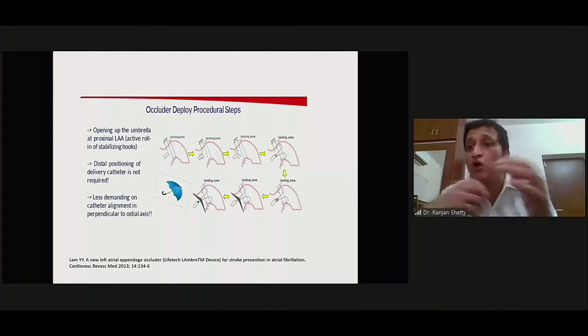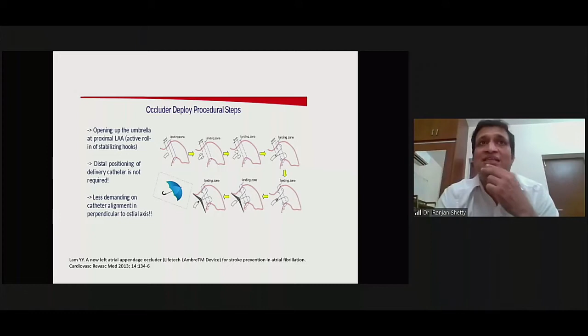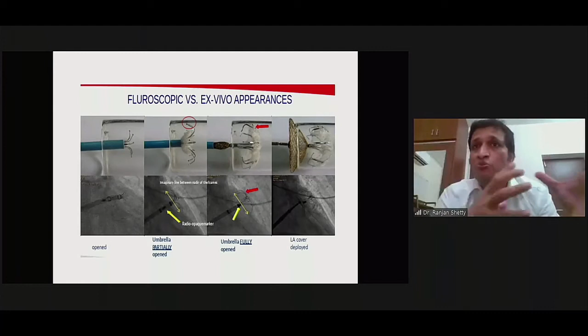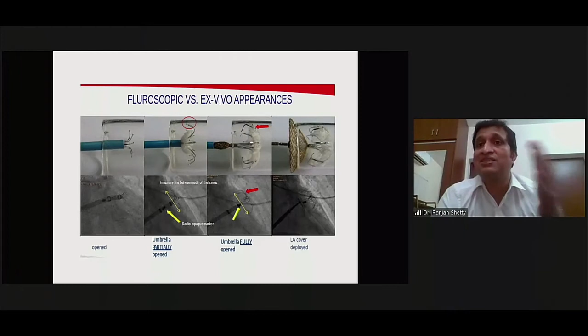Among the devices, this is easy to deploy and it is safer because you're not going too deep, and it's more forgiving. The size variation is allowed, it's a little more forgiving. So just to demonstrate the same thing, you're bringing the hooks out of the sheath here, you're slightly pushing it in, you're reaching the landing zone. As you reach the landing zone, you're unsheathing it further, and more unsheathing will actually lead to opening of the disc. At this point, you find that it's stuck, it's in position, the movement is only in this. So slightly open, partially open, take it to position, keep the anti-clockwise torque, unsheath, and then check whether the lobe is fully covered.